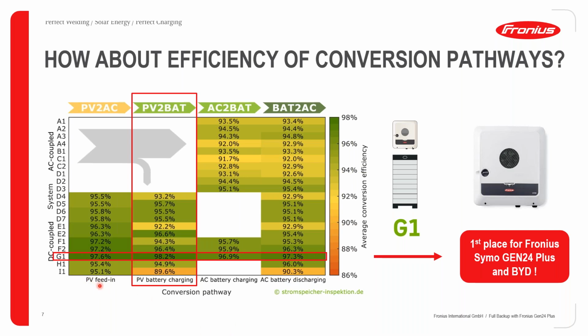Okay, as you can see, the first one was for PV feed-in. Second one is for PV battery charging. Third one is for AC battery charging. So this is where you take power from the grid and you charge your batteries. And the last one is AC battery discharge. So, this is where you take power from your batteries and feed it to the grid. Okay, so you can see with all these different conversions, we kind of achieved an efficiency of greater than 96% when looking at each conversion individually. Again, all our competitors were tested. And again, it so happens that we, again, achieved one of the highest percentages per each of these conversions.